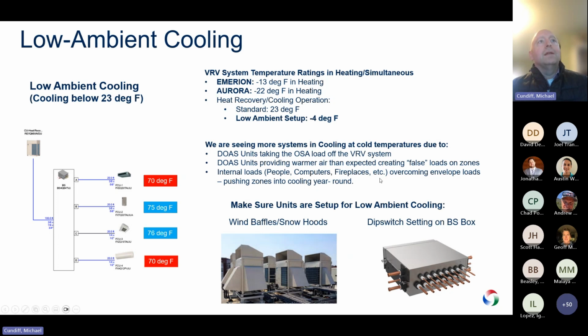All of these combine to sometimes make it so units are really in cooling year round. So for Daikin, what we need to pay attention to is how we set up our low ambient system. Those include wind baffles and snow hoods. We need those when you're going to be cooling under 23. And then we also have a dip switch setting on our BS box that we use. Other manufacturers do this differently. This is how Daikin does it.